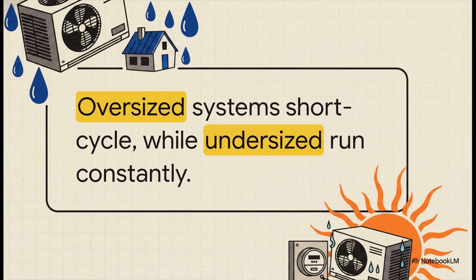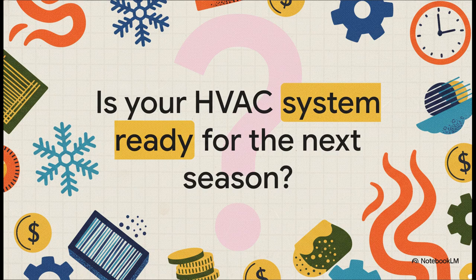So the crucial point here is why precise sizing matters so incredibly much for controlling that massive summer humidity. If a contractor just slaps a huge oversized unit into your home thinking, hey, bigger is better, that system is going to cool the air so fast that it shuts off before it even has a chance to pull the humidity out of the room. It short cycles and your home is left feeling cold, but really clammy and damp. On the other hand, if they undersize it, the machine just runs 24/7, driving up your electric bill like crazy, and you're still sitting there sweating in August. Precision really is everything.